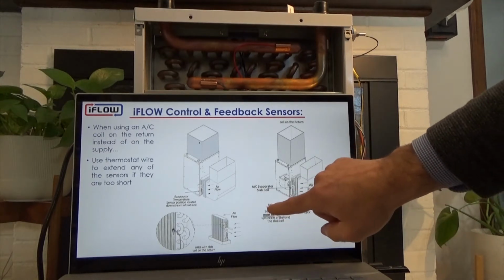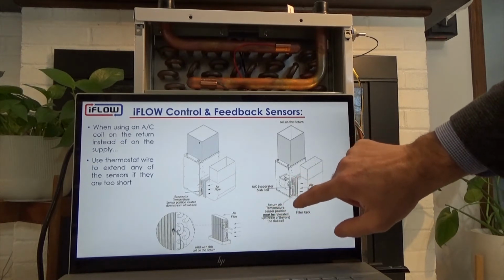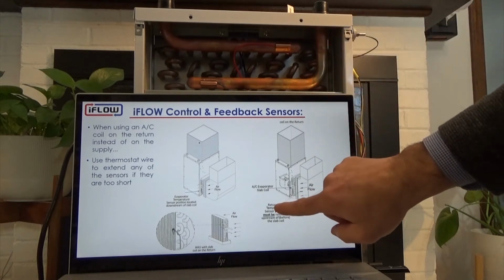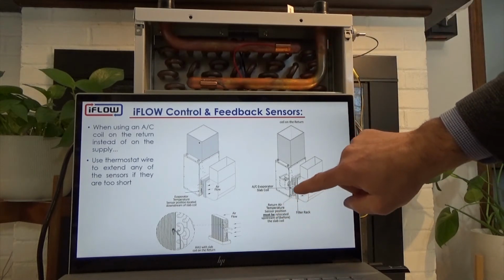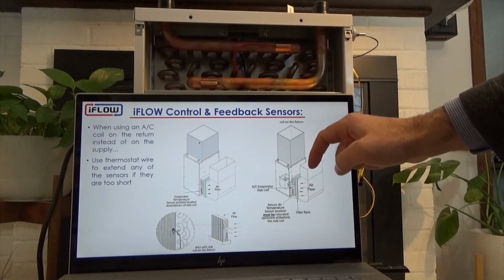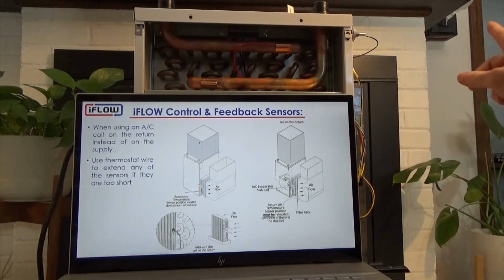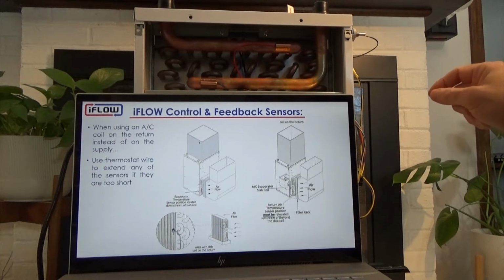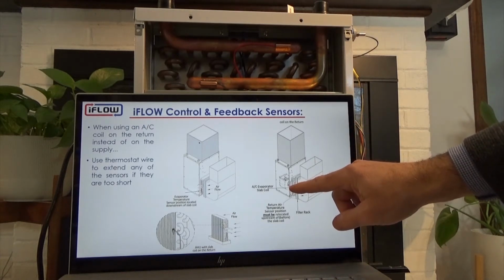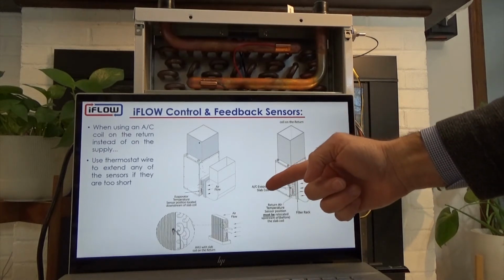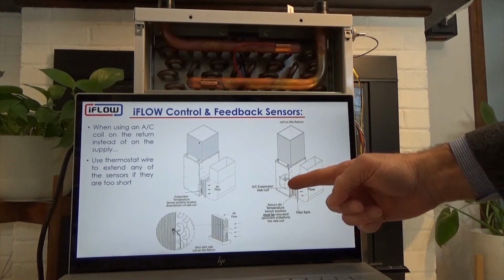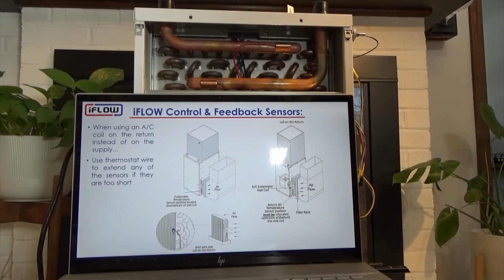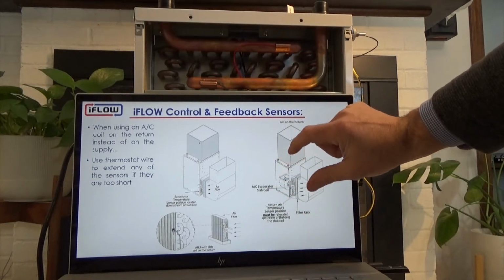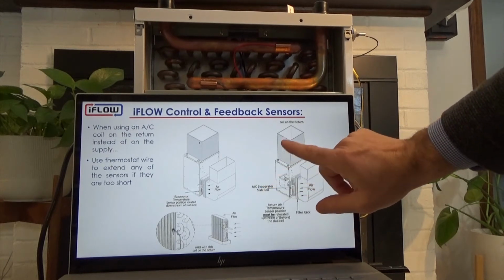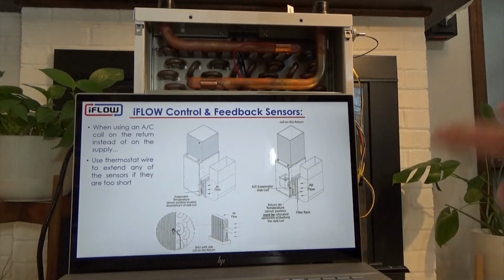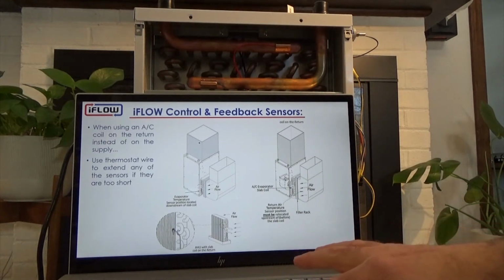So we need to relocate our return air sensor upstream of the slab coil on the return. When we put this into the duct, upstream of the coil, the return air is going to be drawn in, and the sensor is going to see the actual correct room air temperature that's coming back. It will then go through the hydronic coil and cool appropriately, and then the AC evaporator temperature sensor is going to see that chilled air, and the system will work properly. So when we're using a slab coil on the return, it's important to relocate not only the evaporator temperature sensor, but also the return air temperature sensor. And again, both can be extended using temperature or thermostat wire.